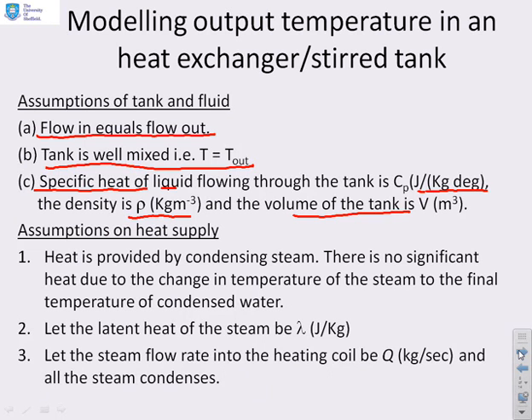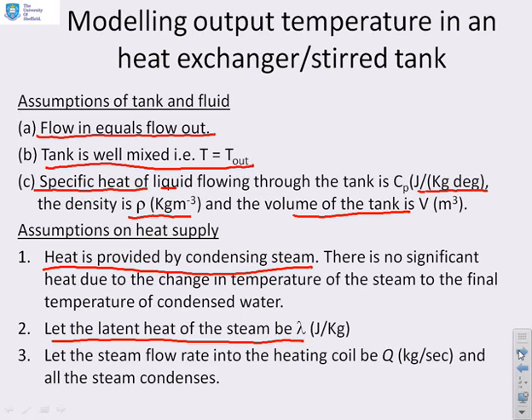For this video we are going to assume that the heat is provided by condensing steam. Once the steam is condensed, the resulting water will continue to reduce in temperature and therefore provide some energy. However, we're going to argue that the amount of energy provided by the cooling down of the steam is negligible compared to the latent heat, so we're going to ignore that — it's probably of the order of magnitude of 10 to the minus 3 and therefore not really significant in terms of a model. Let's assume that the latent heat of the steam is lambda, in joules per kilogram, and we're going to let the steam flow rate into the heating coil be Q, in kilograms per second. We're also going to assume that all the steam condenses.